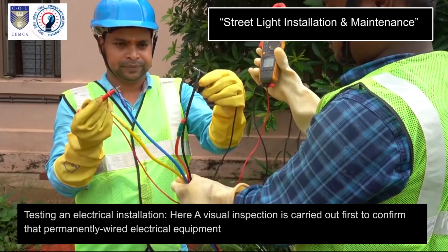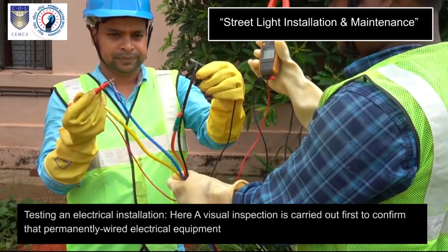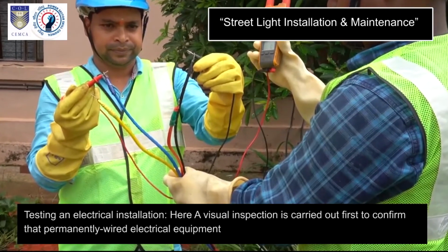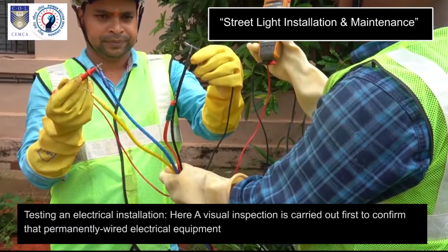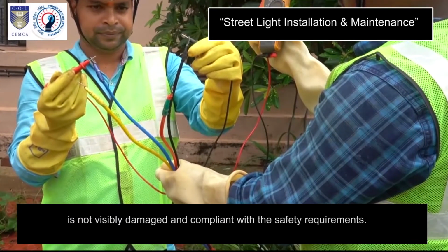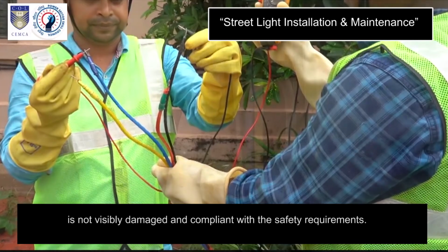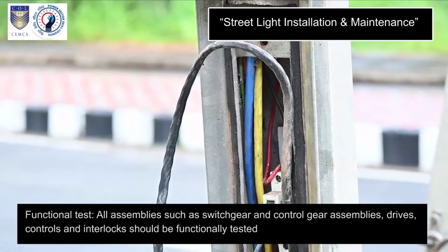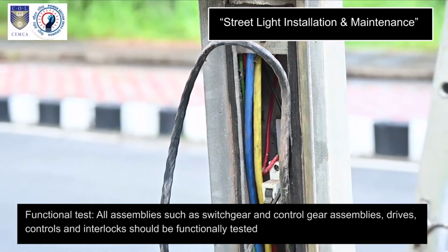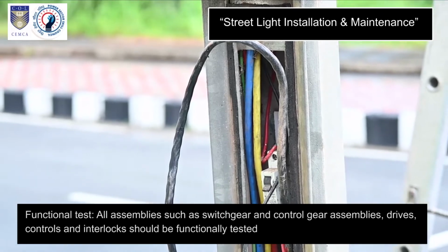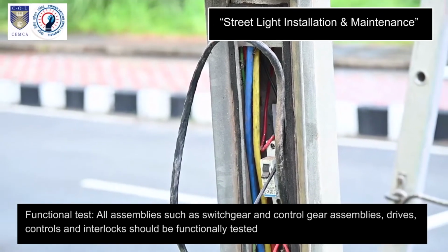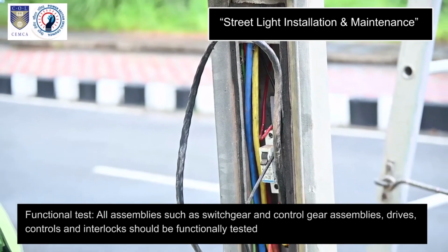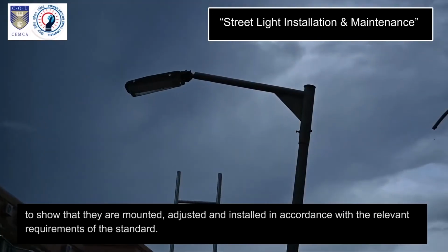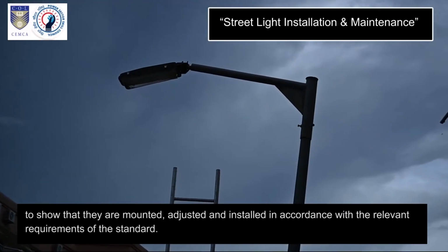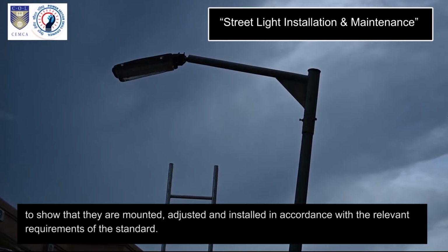Testing an electrical installation. Here, a visual inspection is carried out first to confirm that permanently wired electrical equipment is not visibly damaged and compliant with the safety requirements. Functional test. All assemblies such as switchgear and control gear assemblies, drives, controls and interlocks should be functionally tested to show that they are mounted, adjusted and installed in accordance with the relevant requirements of the standard.